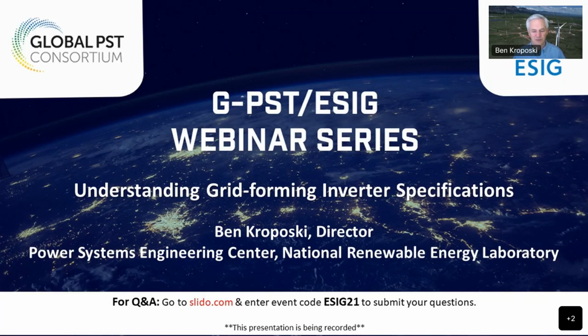I think the biggest challenge we have is the fact that grids of the future are going to be transitioning from synchronous generator dominated to inverter dominated and back and forth, probably for the next decade or two, maybe into the foreseeable future. So addressing all of those issues around short circuit is going to be a challenge for a high inverter-based grid, and we're going to have to come up with some devices in there that provide that short circuit current if we want to keep the existing protection system. If we want to redo a protection system, we may have different options to address that challenge.